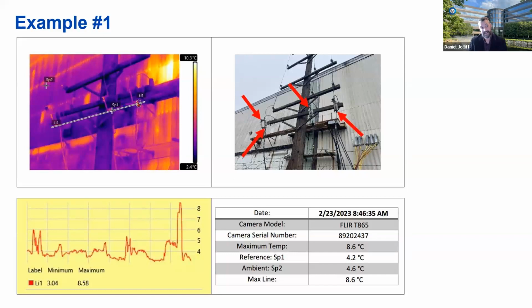What you see on the left image is one of our standard thermal images. We've got a breakdown and synopsis of the specific temperatures and specific spots. And what we have is a histogram line that's been drawn across all 3 phases, all 3 of these high voltage fuse clips. And as you can see, in the histogram temperature chart right below the thermal image, we have spikes. This is obviously something that's somewhat concerning. We don't want to see these spikes in temperature.